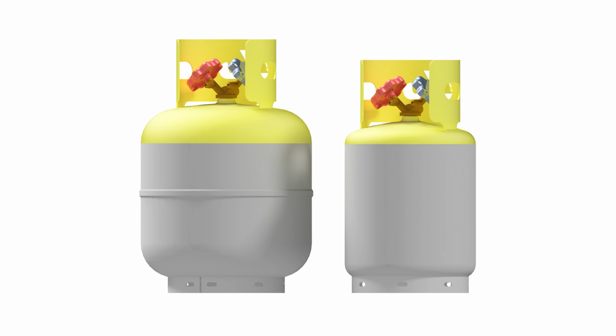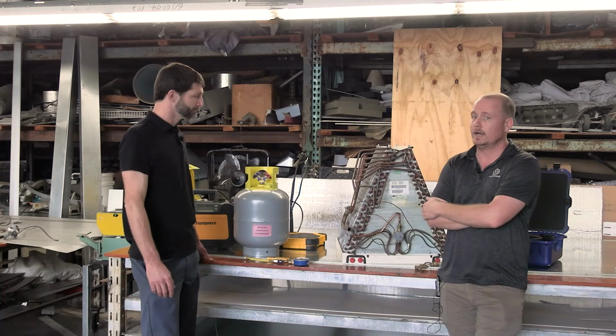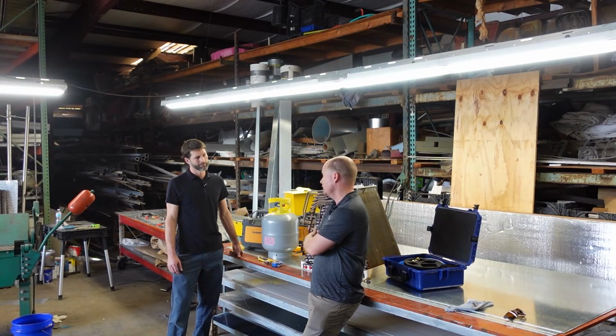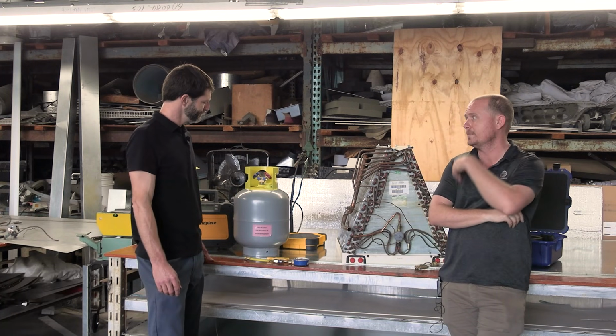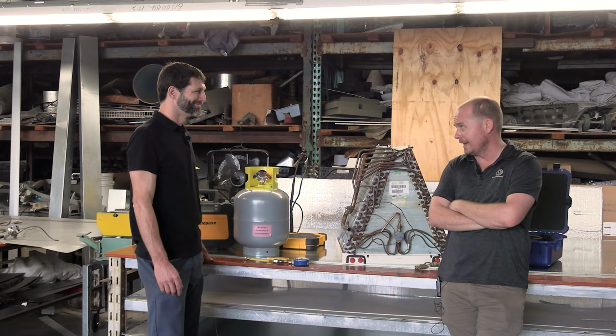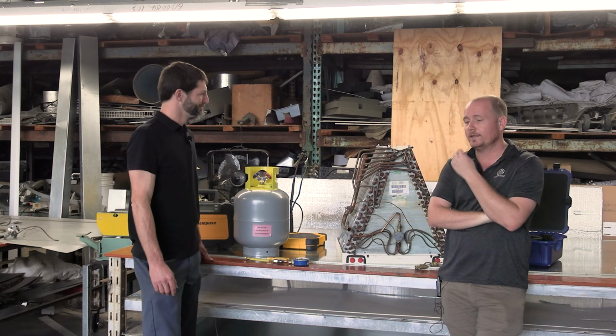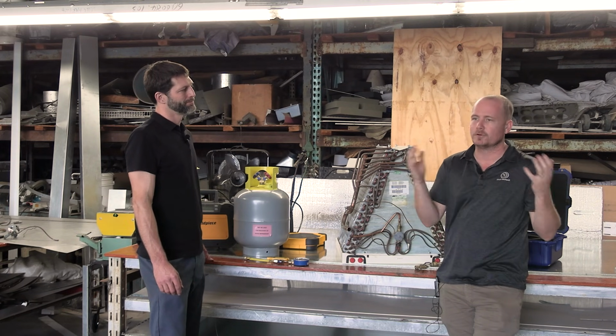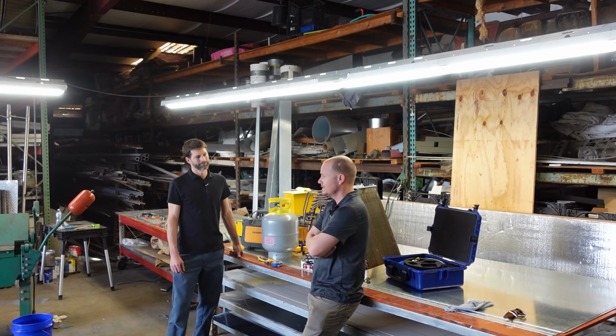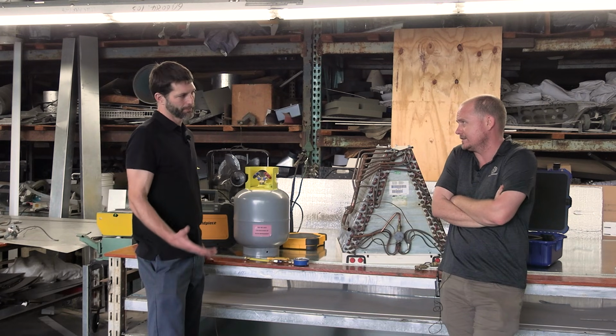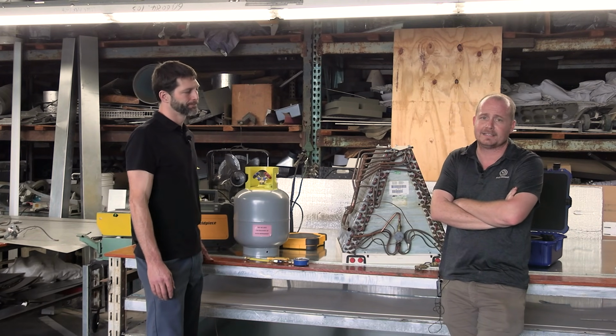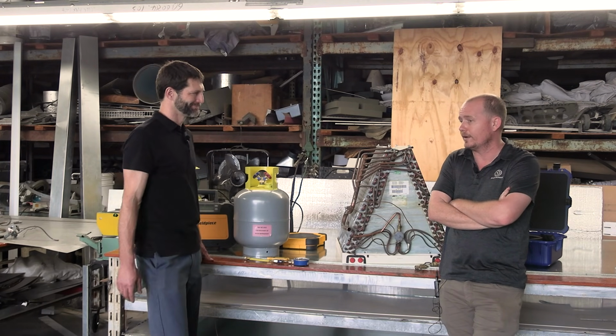And that's another thing. Some people are always using the smaller tank sizes. And if you are working on a 5-ton piece of equipment, for example, that's holding potentially 20 pounds of refrigerant, that's probably not your best bet. So in general, most of the systems we're doing, because we do a lot of change-outs, our recoveries typically take 10, 15 minutes. That's going to be typical. If you're finding that it's taking an hour, well, then there's probably something going on there.